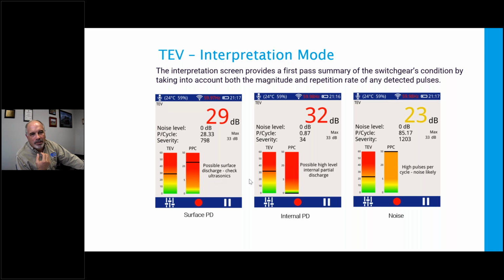I talked about our interpretation mode. We've got ultrasonic here. It tells, because of this pulse count, 28 pulses per cycle. I told you half an hour ago that means it's probably ultrasonic, probably surface discharge. So it tells you use ultrasonic. That's more sensitive than TEV. Here I've got a nice high level. I've got a pulse count that's just under 1. That's likely internal discharge. Here it's pretty high, but my pulse per cycle count's too high for PD. So I'm going to say that's probably noise. Just trying to help you along.